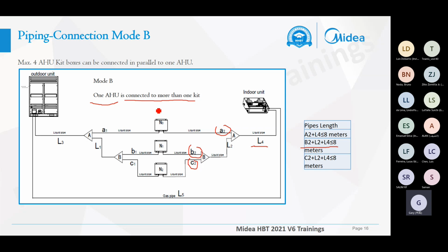When we connect more than one kit to one AHU, we should select one kit as the master AHU kit, and set it after selecting. This is a very important part. As in the next part on wiring, the master AHU kit will have a different sensor placement from the slave kit. And the part we should pay more attention to is that the distance between the AHU kit and the AHU should be less than 8 meters.